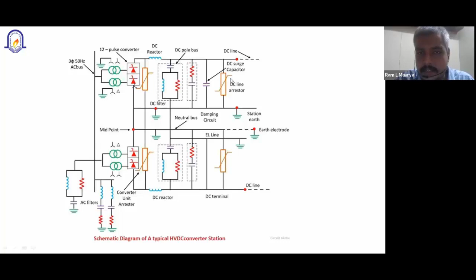The advantage of HVDC is that there is no reactive power, so long transmission lines can be laid. Transmission capacity is almost 3 times that of AC for the same infrastructure. There is less corona loss. There is corona loss in lines also, and electrical engineers know this corona. So there is lesser corona loss and radio interference with DC.